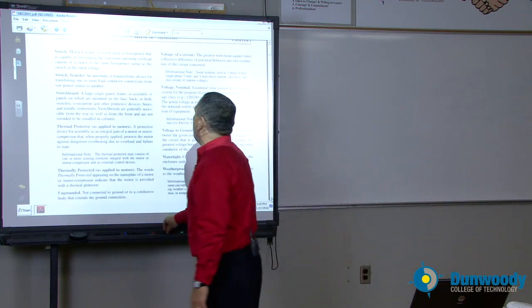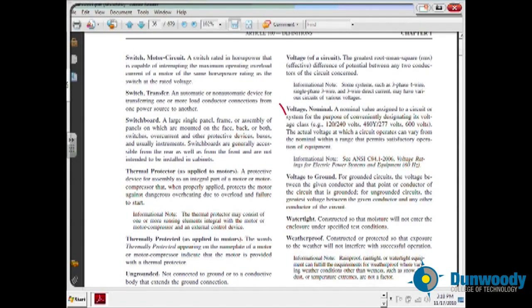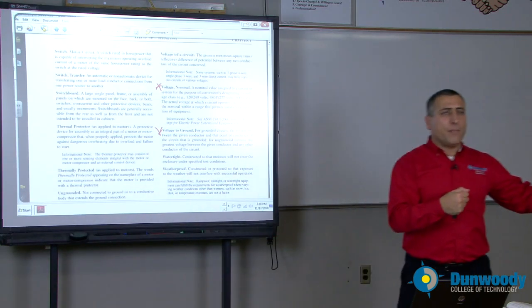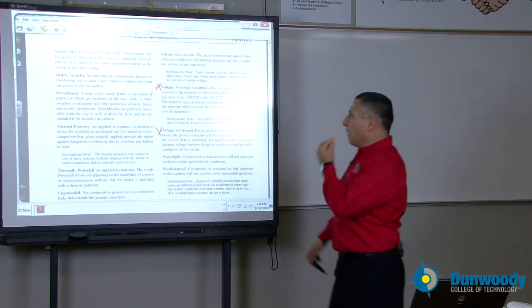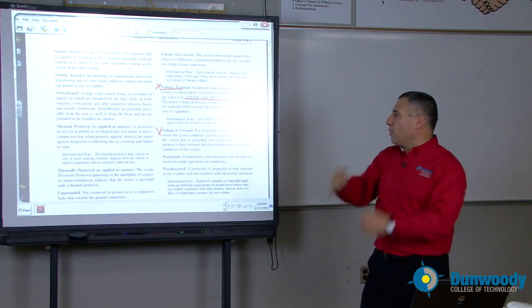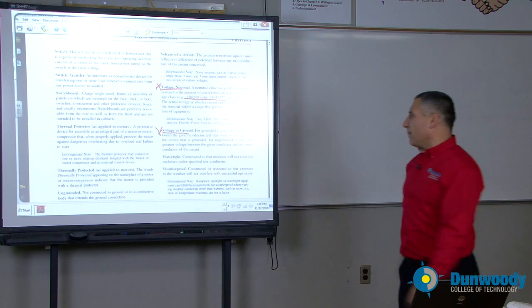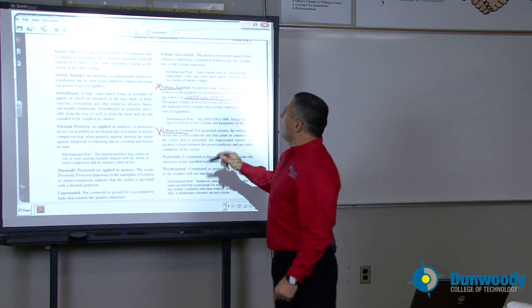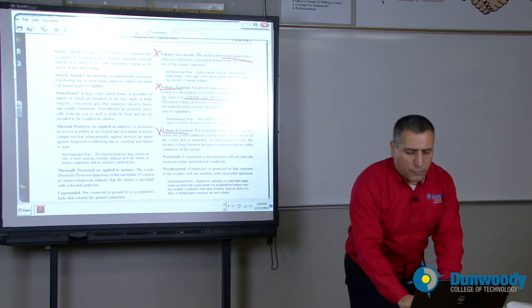A few other things I'd like to highlight: voltage nominal and voltage to ground. Voltage nominal is an assumed voltage — if you see nominal 120/208, that's the nominal voltage. If you measure it, it might be less or more. These are just an assumed voltage, not actual voltage. The actual voltage could be less or more. Voltage to ground in a grounded system is measured between the hot conductor and the grounded conductor. And the voltage of the circuit is the RMS value.